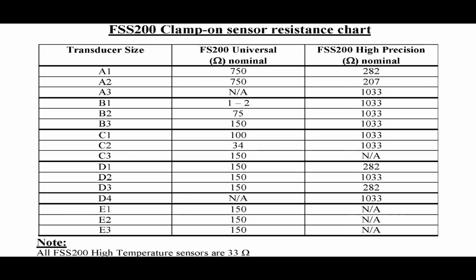Again, here is the table that lists the two main types of flow sensors and the resistance values for each size that you should see when you measure using this technique. Don't forget that there will be a few additional ohms depending upon the length of your cables. The key thing is that the upstream cable and the downstream cable should more or less read exactly the same resistance value.